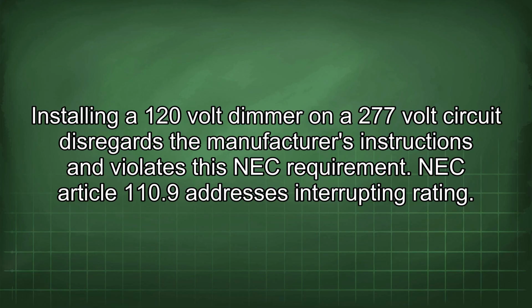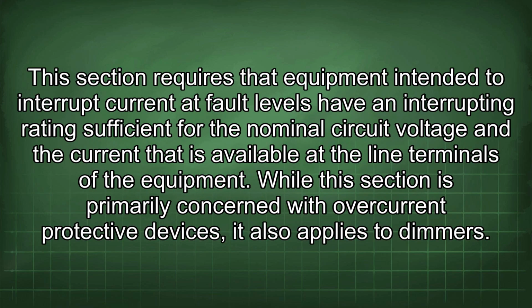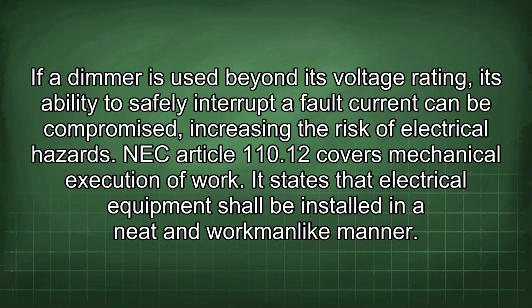NEC Article 110.9 addresses interrupting rating. This section requires that equipment intended to interrupt current at fault levels have an interrupting rating sufficient for the nominal circuit voltage and the current that is available at the line terminals of the equipment. While this section is primarily concerned with overcurrent protective devices, it also applies to dimmers. If a dimmer is used beyond its voltage rating, its ability to safely interrupt a fault current can be compromised, increasing the risk of electrical hazards.